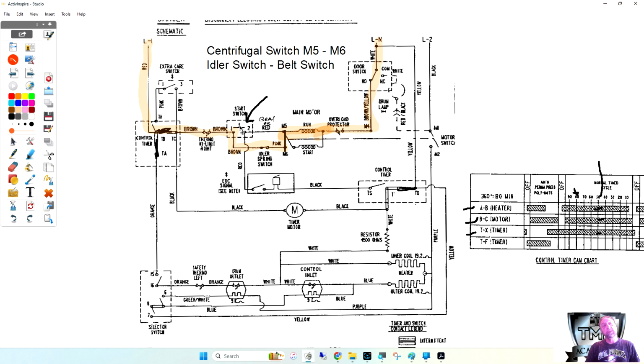Now, could someone think the start switch is bad if you pressed it down and the motor didn't continue to run? Could it possibly be a start switch? I'm trying to find, I have you guys on one of my screens and I can't figure out which window I have open for you. There we go. Well, if you have continuity on the switch when you test it, would it show that it's functioning at that point? It's functioning when you're pressing it down, but the problem is you need to know what type of switch that is.